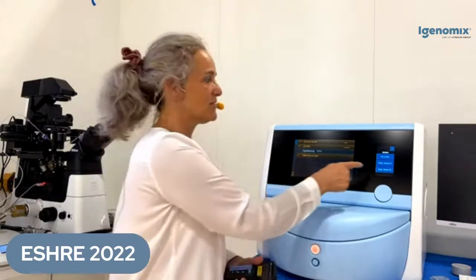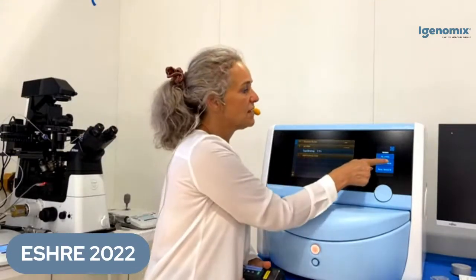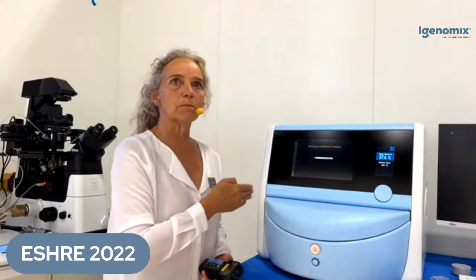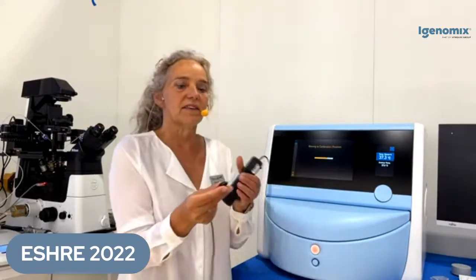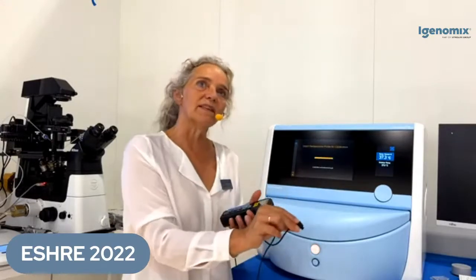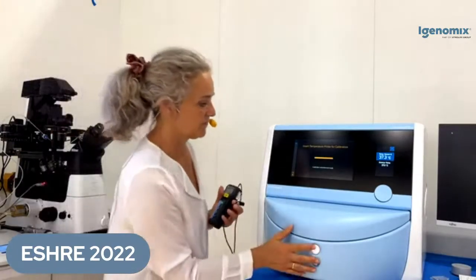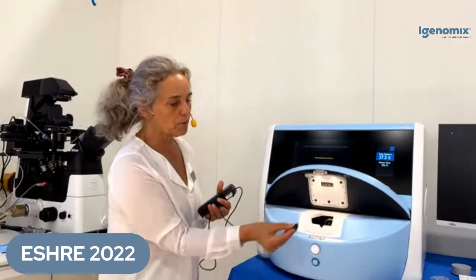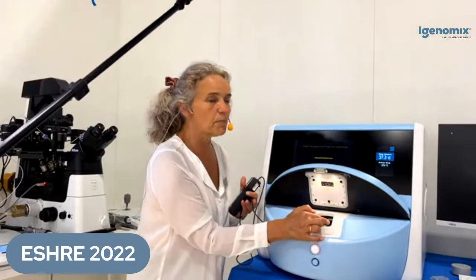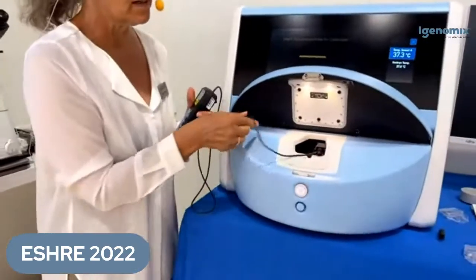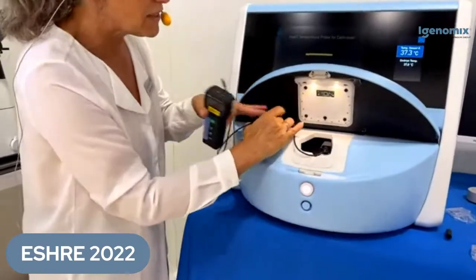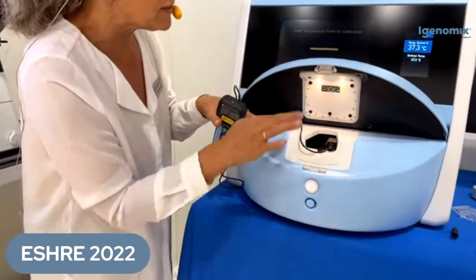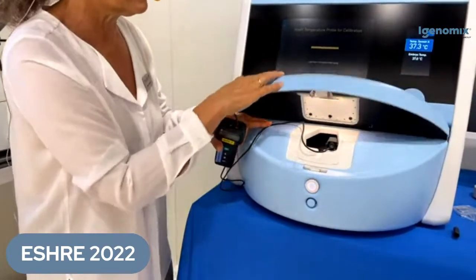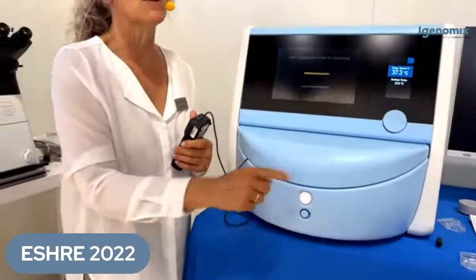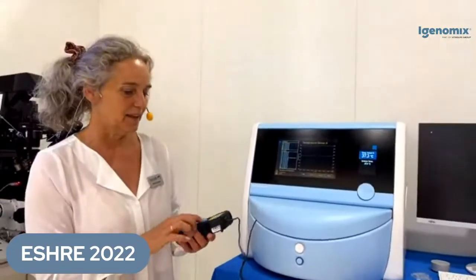But for this demo, I will just show you from temperature setting. So I press here on A, and this rotating plate will now move to this area where I can insert the probe. This is a channel that goes next to where the embryos reside when they are cultured. So I put the probe in here, and it is important that it is completely in this channel. While I'm closing the load door, it's always a good idea to put the cable up here. If the measurement is really out of range, I would check if it's going out of the hole. Yeah. And then I start the measurement.